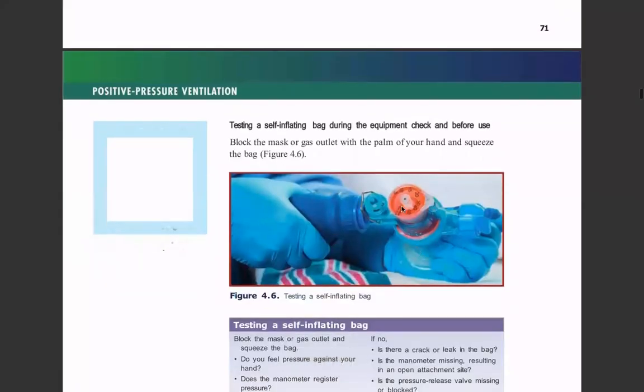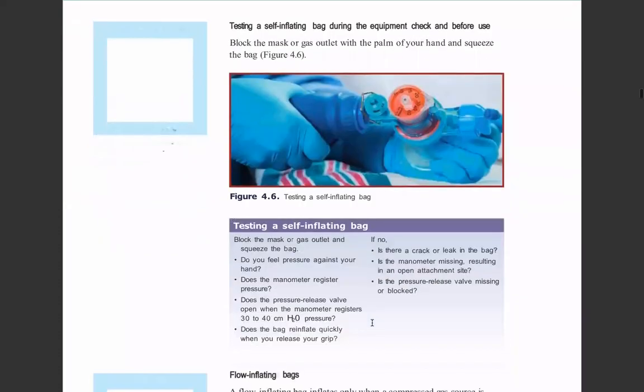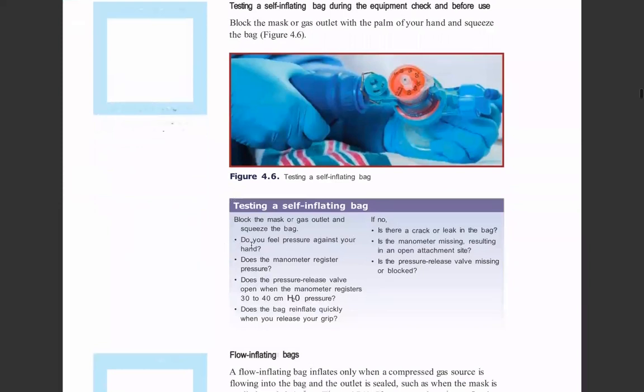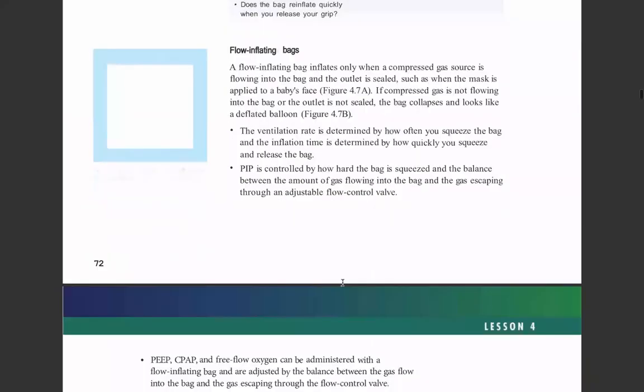This is how to test the ambu. This is a pressure gauge. This is your pop-off valve. If the pressure goes above 40, it will open up so that you don't give more pressure to the baby. This is also called a self-inflating bag, which is a technical term. Usually at 30 to 40 centimeter of water the pop-off valve will open up. That is the maximum required for the baby.